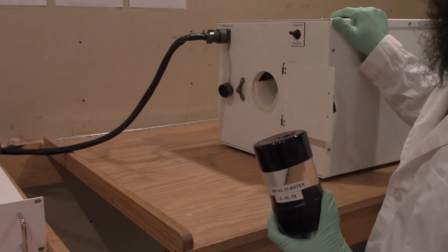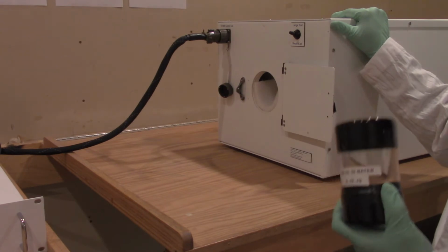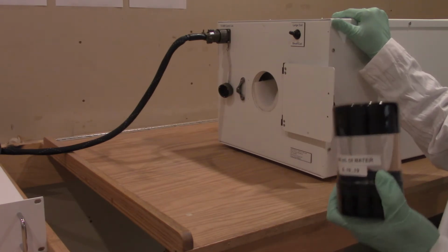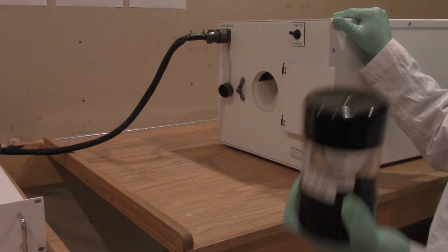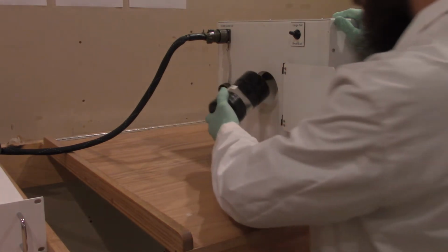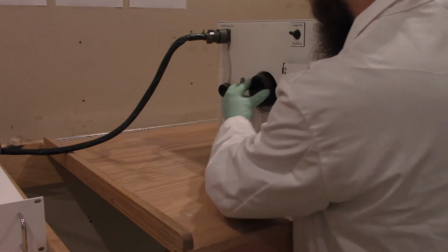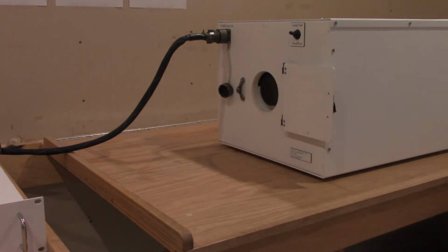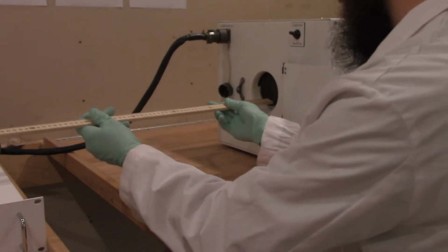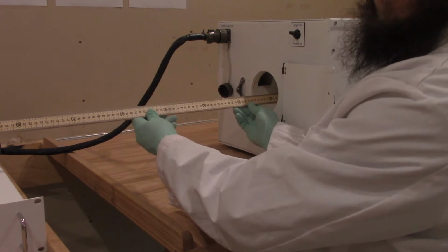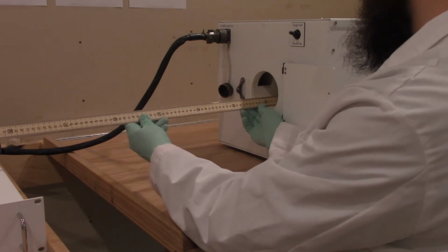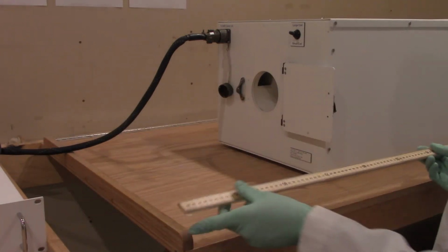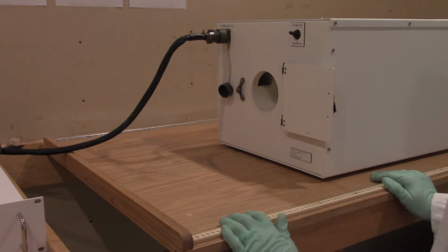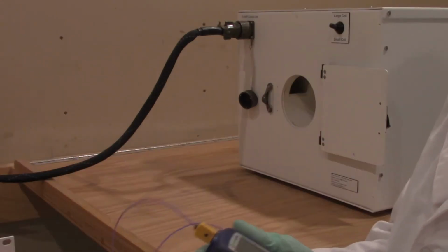The second point is that the positioning inside the sensor is critical. You want the sample to be at the same position in the instrument for every single sample and for the calibration blank. To do that, we can just measure with a ruler. We'll put our sample in and then make sure the position is correct. We take our ruler, and in this case, the sample is centered when it's 20 centimeters from the end of the instrument. So each sample is going to be put into that same position.